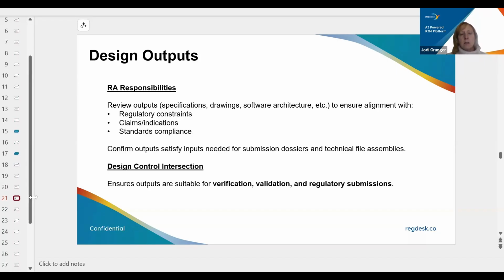Next is in terms of design outputs. So regulatory will take a role in really reviewing the design outputs that start to be generated. Any product specification documents, drawings, your software architecture, etc. Each of these reviews will ensure that you factor in any regulatory constraints, that you understand what claims you're going to be able to make on the product, what indications you're going to have, that you're going to be able to comply with specific standards. And again, you want to make sure that all of the documents that your cross-functional team are creating are aligned with the regulatory strategies that have been put into place. These all feed in to your verification and validation, which help to support your regulatory submissions.